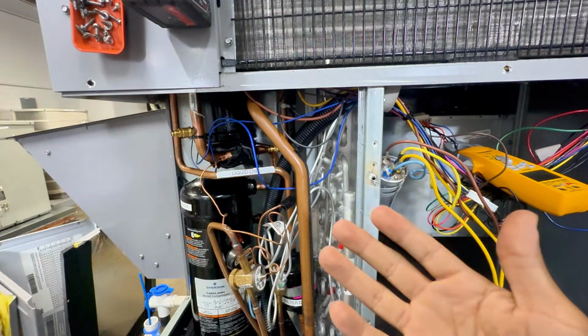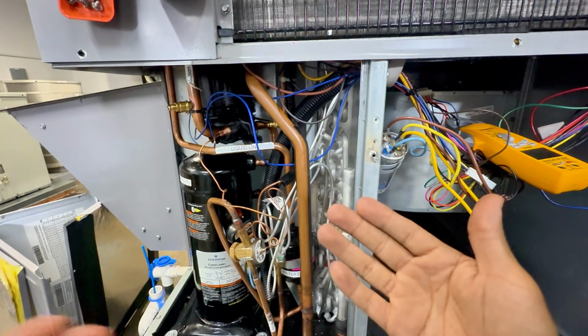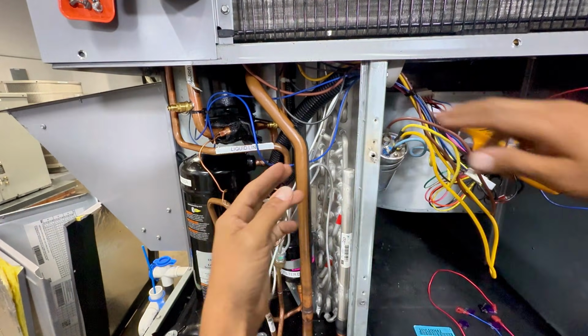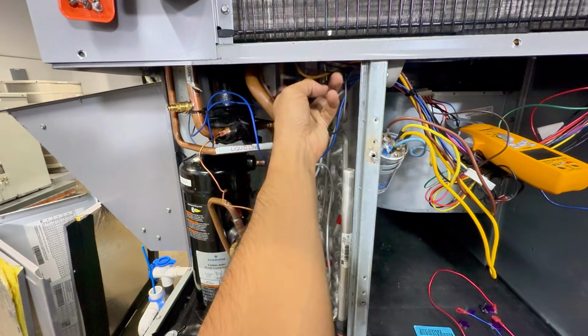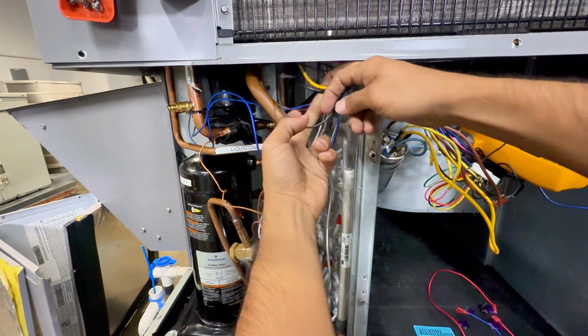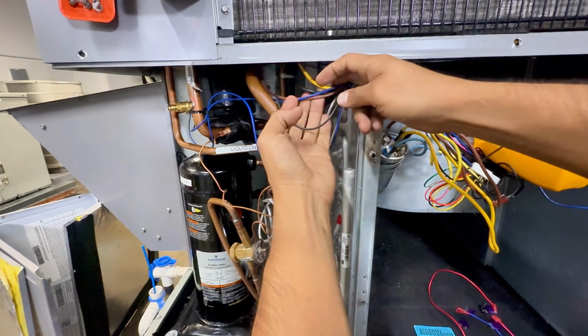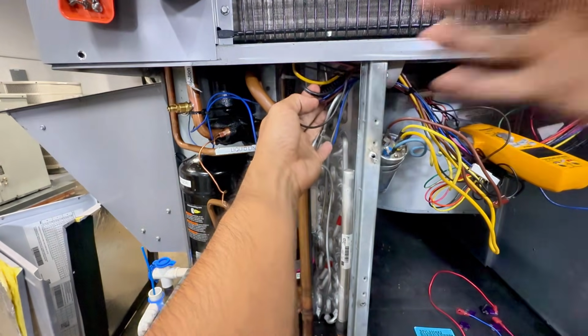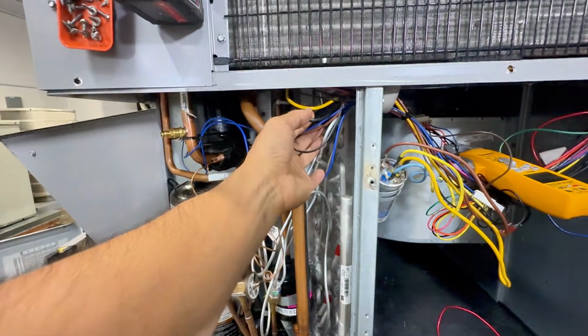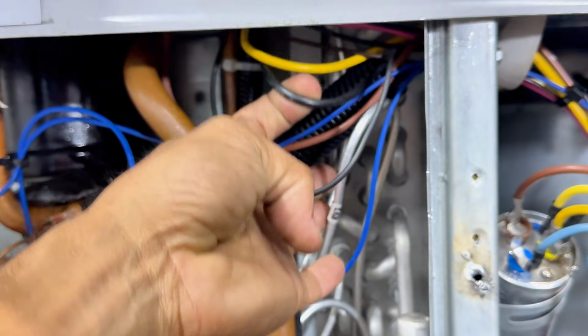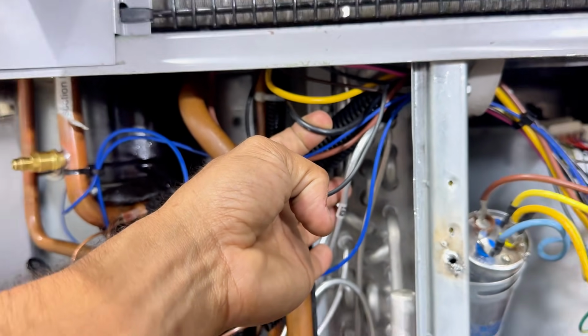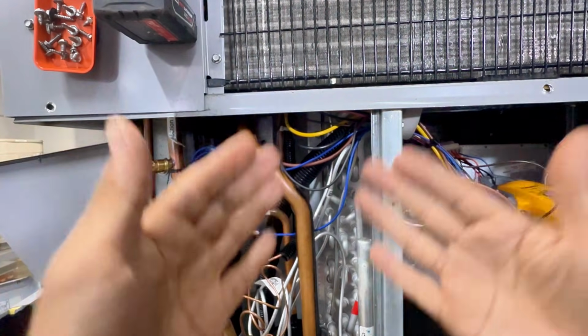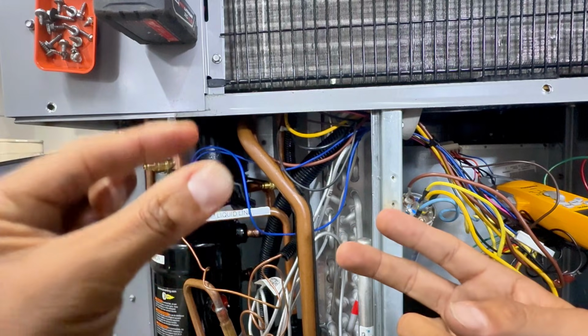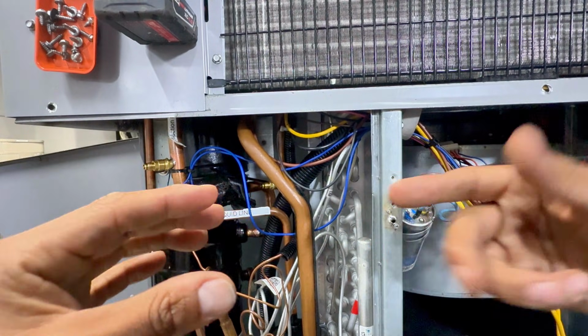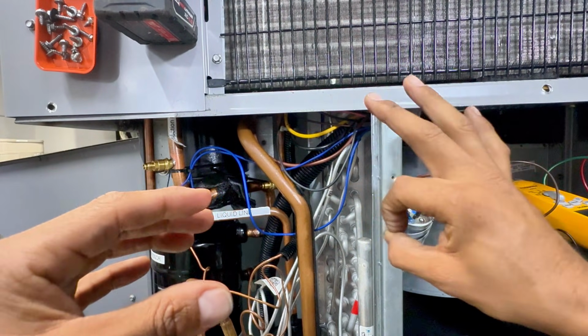So if you're able to watch the video on resistance, on that video, I was able to trace out the 3 wires that go to my condenser fan motor, which is this yellow one, this black one, and this brown one. And I was able to specifically point out that my black one here was my common, right? Remember, PSC motors have 2 windings, run winding and start winding, and the wire that they share in common is your common. So that's the one you want to check it on.